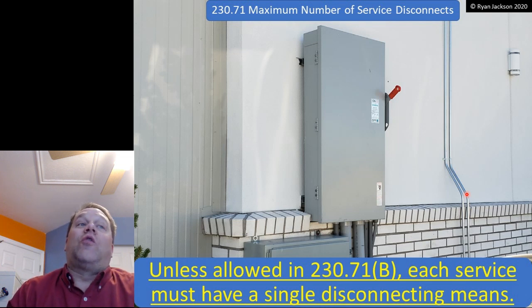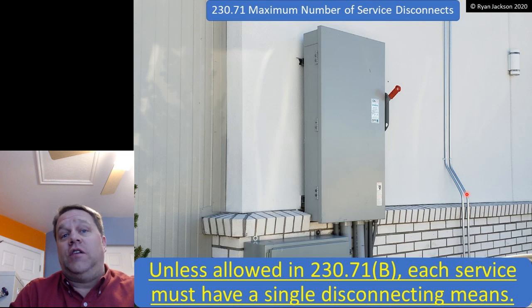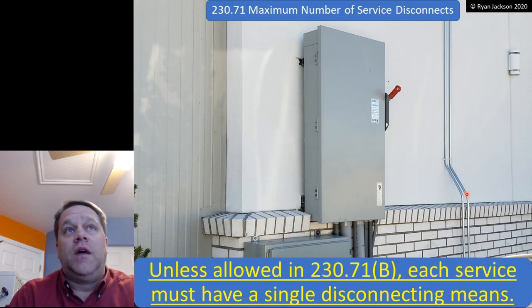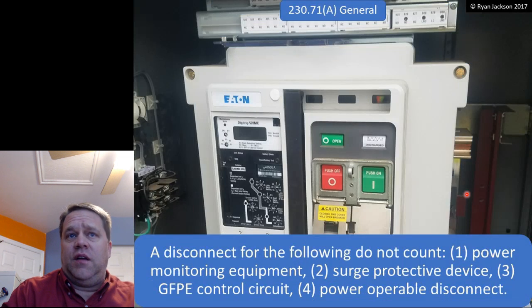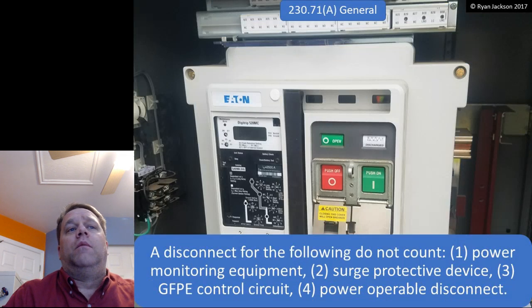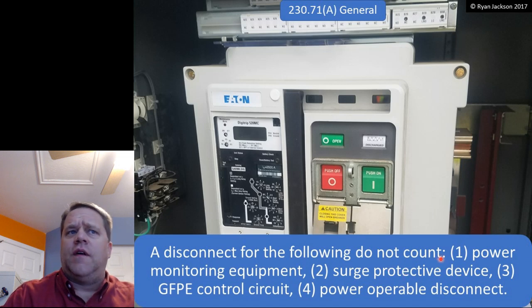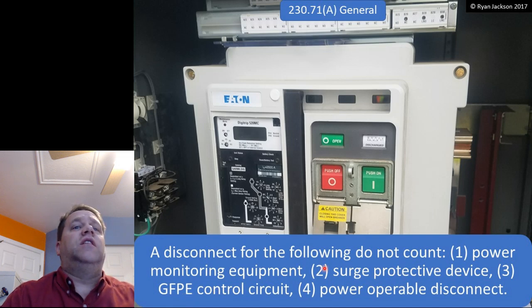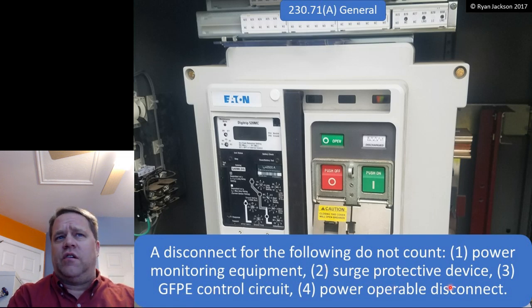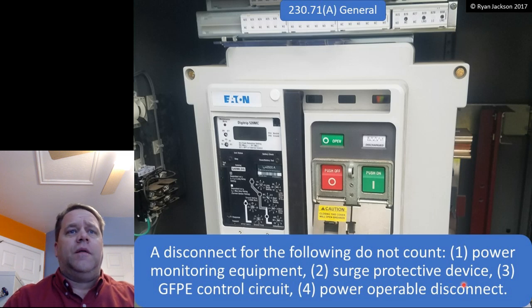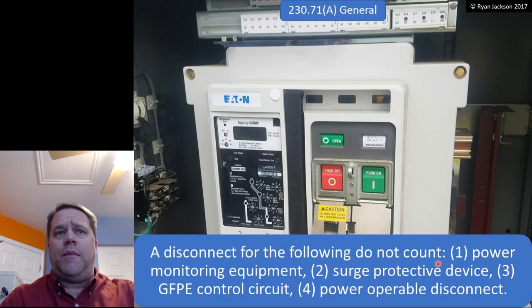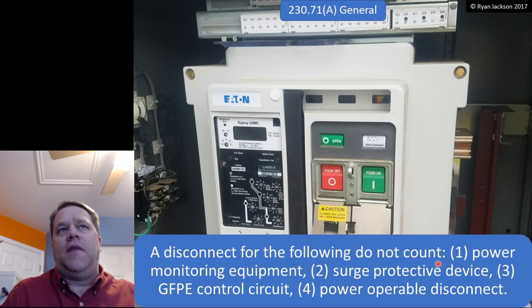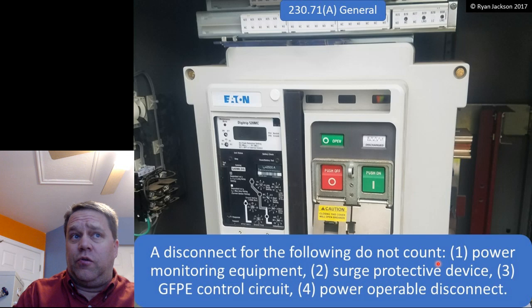So, quite literally since 1897, the first edition of the code, we've been able to have more than one service disconnect. This is absolutely new territory. Now, just so we're on the same page, a disconnect for power monitoring equipment, a surge protective device, ground fault protection of equipment control circuit, or a power operable disconnect, these are not considered service disconnects. So if I have power monitoring equipment in my panel and it has its own little shutoff, that's fine. That doesn't count.